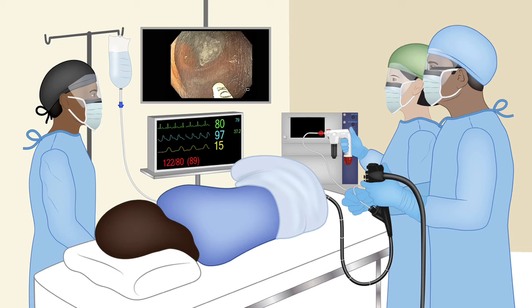If the catheter gets plugged, you may not be able to deliver any more of the Hemospray. In that case, one needs to remove the catheter out of the endoscope and then flush the channel with air to dry it, and then reinsert a new catheter, going through the same steps of flushing the catheter repeatedly with air as it's going down the channel, and avoid the urge to apply suction.